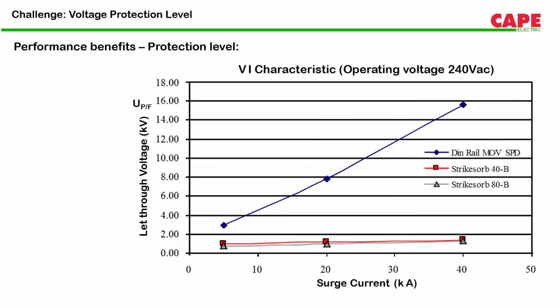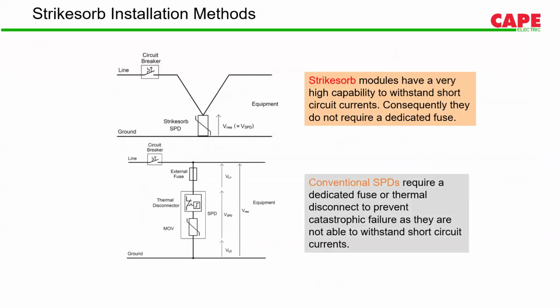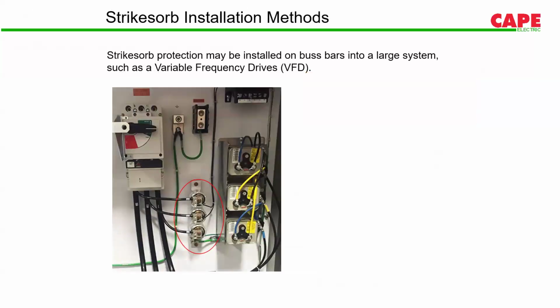This is a let-through voltage graph of two SPDs. One is a DIN rail mounted SPD, the second is the Strikesorb series SPD. As you can clearly see, for a DIN rail mounted SPD, the let-through voltage increases drastically, almost exponentially, as the surge current increases. Whereas in the Strikesorb series SPD, the let-through voltage is almost constant, whatever the surge current is. This is how Strikesorb SPDs are connected in the bus bar, whereas DIN rail SPDs are connected with an external fuse. These are some installation photos of the Strikesorb series SPDs.